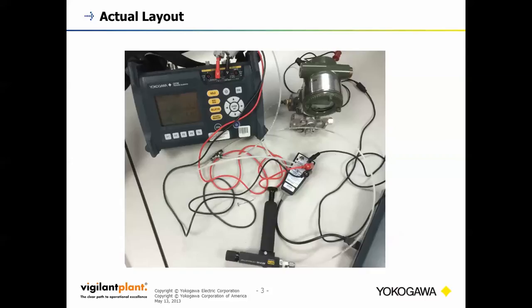So here's the actual layout of a calibration I did. Looks a little kind of messy, but I'm going to try to clear things up with some highlighted boxes to better display the connections that we're doing here. So again, we've got our CA700 pressure calibrator. We've got an EJA110E differential pressure transmitter that we're going to be calibrating. We've got our pressure generating pump that is connected to both the pressure transmitter and the calibrator.